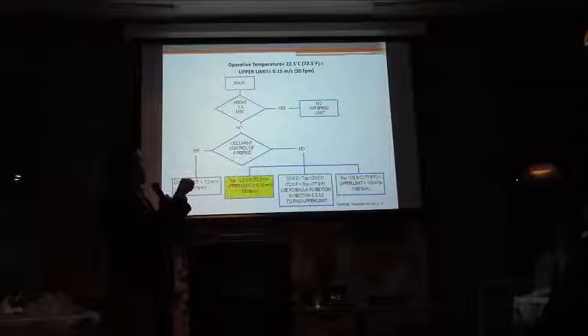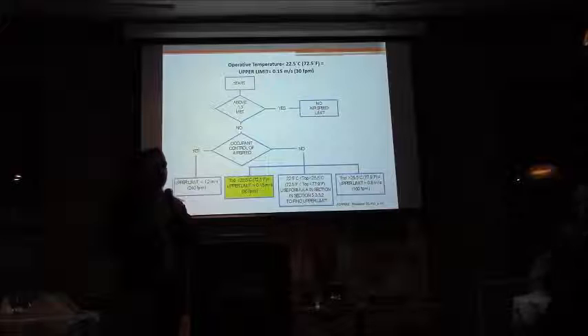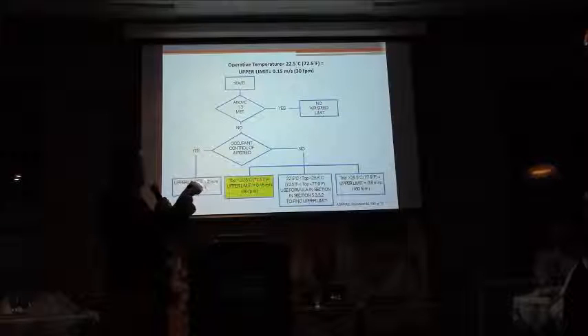So if your metabolic rate is lower than 1.3, the second question is, do occupants have control over the airspeed? If the answer is yes, then you have a maximum of 240. But I've never seen an application where people could control the speed of their HVAC system. So you fall into the no category, and if your temperature is under 72.5, the maximum velocity is 30 feet per minute.